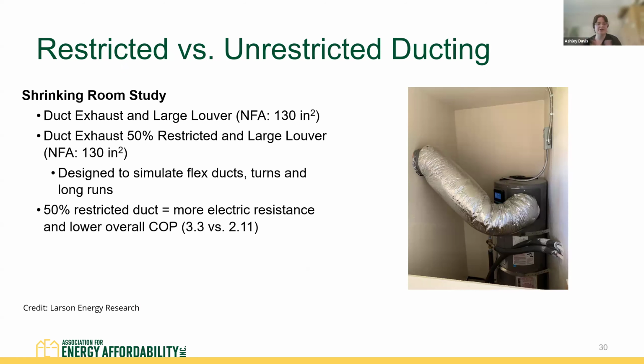If you're going to duct, though, it's really important that your ducting is unrestricted, right? You can see a picture on the right here of a unit that has a ducted exhaust, but there's a pretty big kink in the duct, and it's doing a hard 90-degree turn right after it comes out of the water heater. So there's a shrinking room study, basically, where some researchers tested a bunch of different ventilation configurations to see which one led to the best performance.